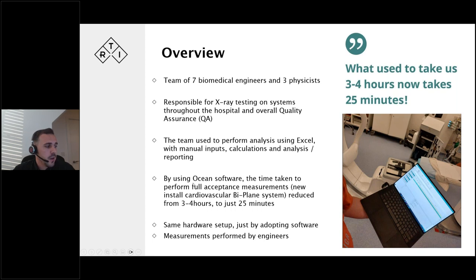So we're going to look at how they transitioned to using Ocean software, which allowed them to perform a full acceptance test on this system, and of course many others, reducing the time taken from 3 to 4 hours to just 25 minutes. That was using the same hardware setup and just maximizing the efficiency of the software.